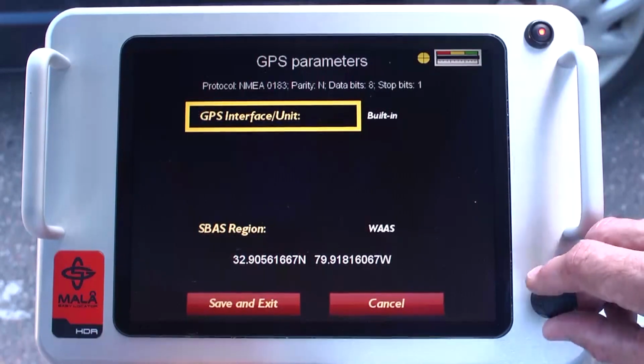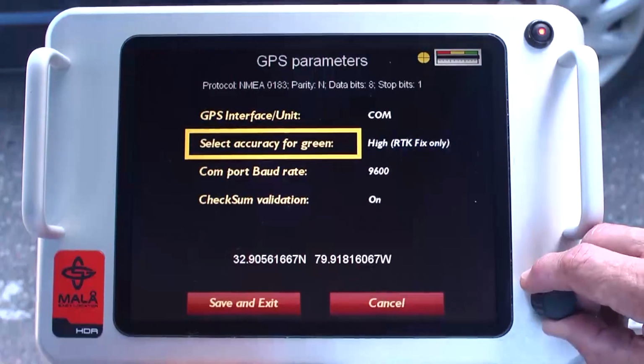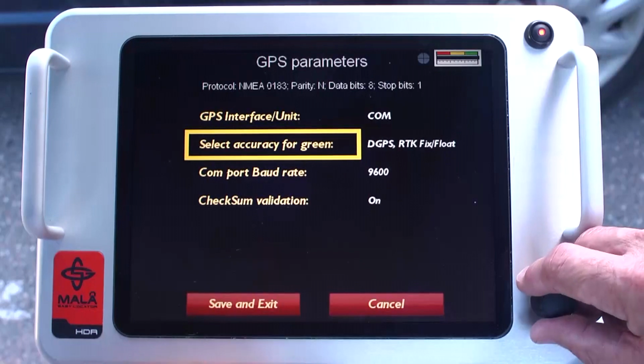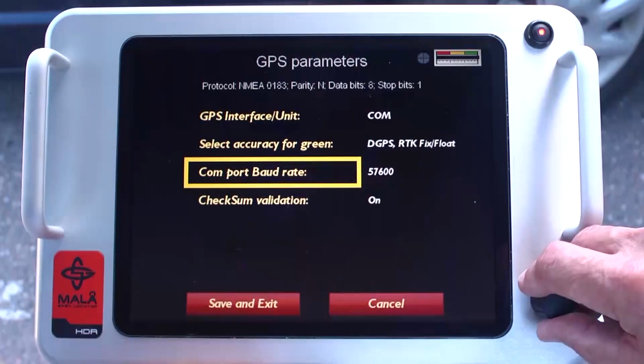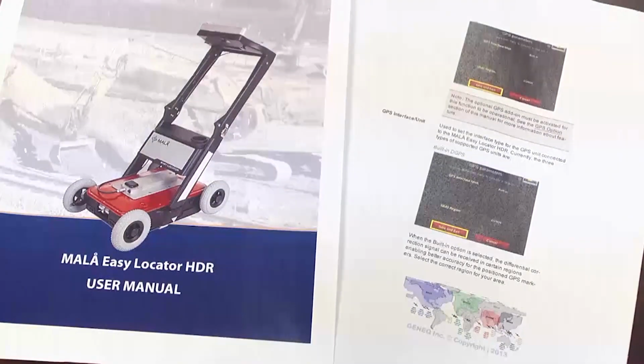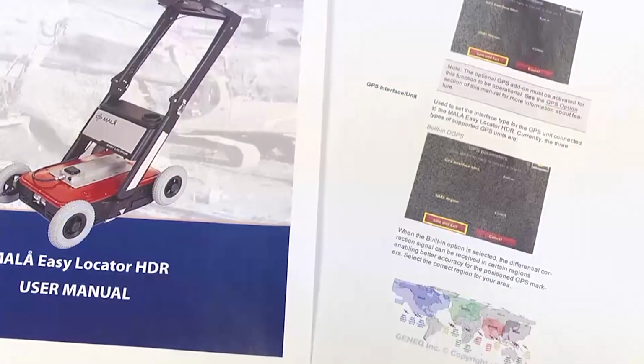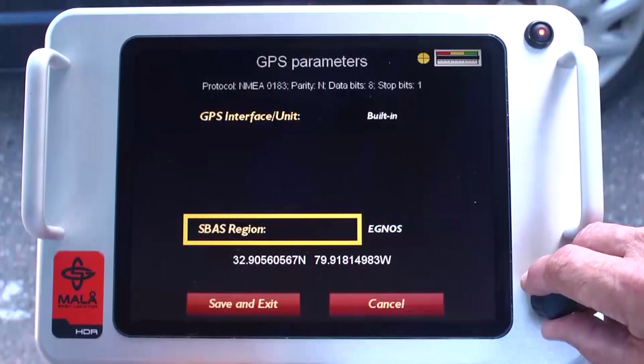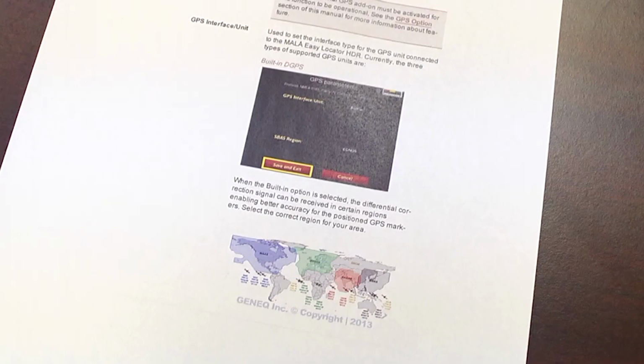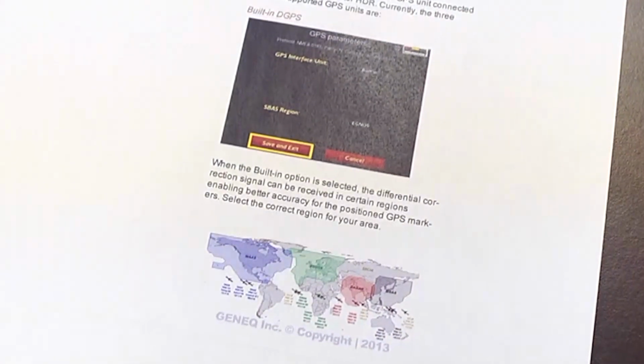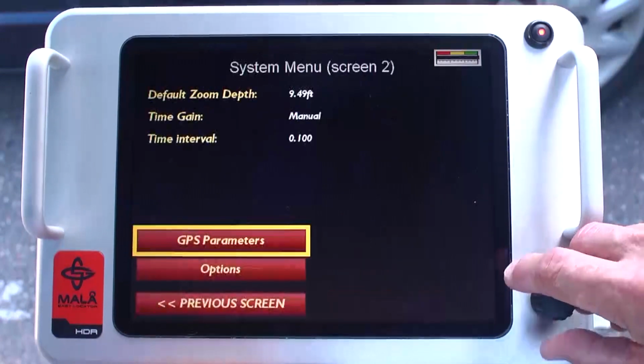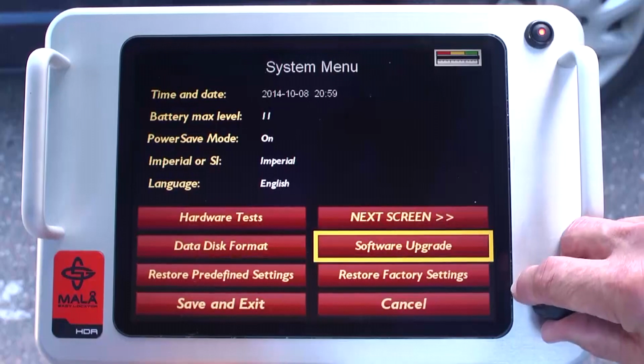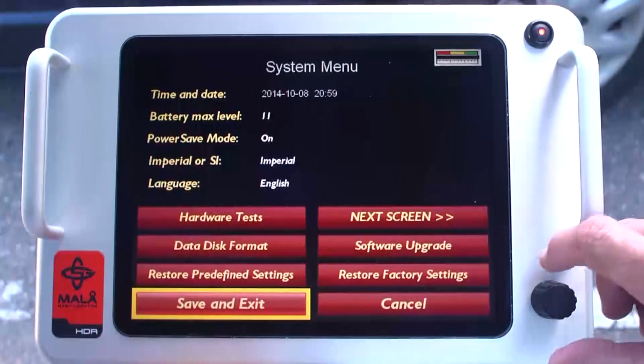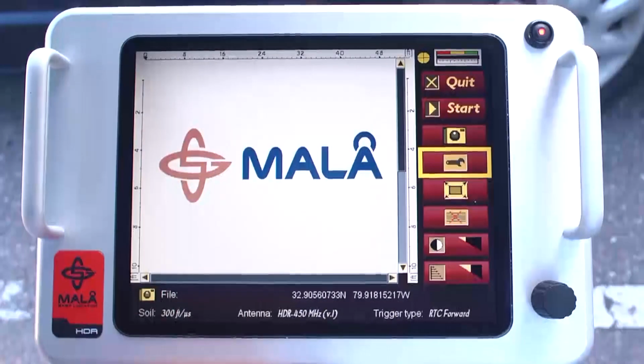Select by toggling between built-in, USB, or COM. If COM or USB is selected for an external GPS receiver, default settings are normally adequate. For additional instructions on connecting an external GPS receiver, please refer to the MALA Easy Locator HDR manual and the GPS manufacturer's manual. For built-in optimal accuracy, select WAAS for U.S. customers. And for regional coverage outside of the U.S., consult the manual for the appropriate GPS coverage using the SBAS region menu. After selections, select Save and Exit. Then select Previous Screen. Then select Save and Exit. Then select Save, which will return you to the acquisition screen, at which time you will see the GPS coordinates appear on the bottom of your screen.